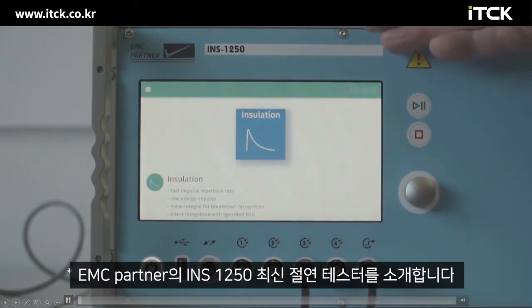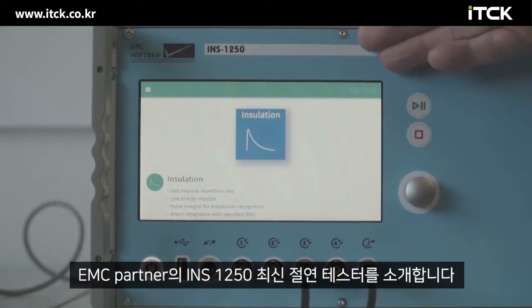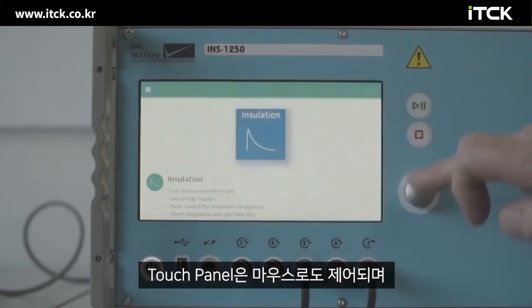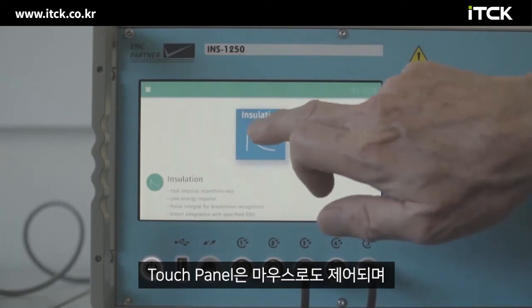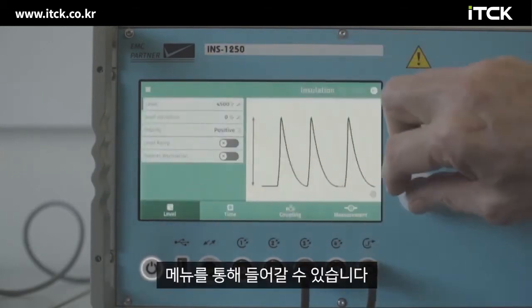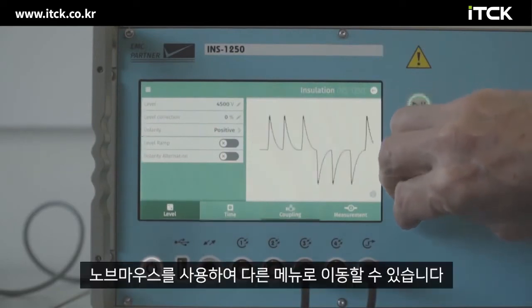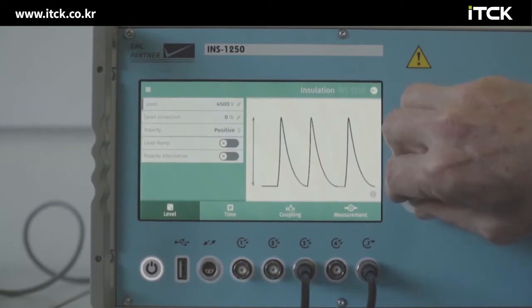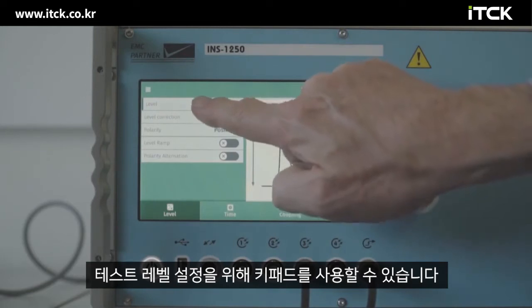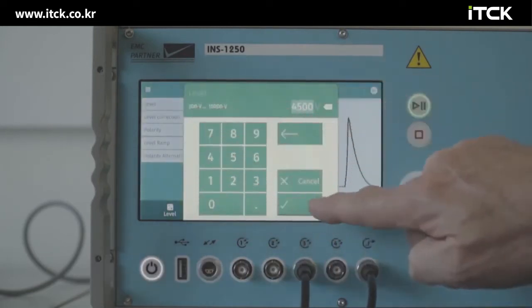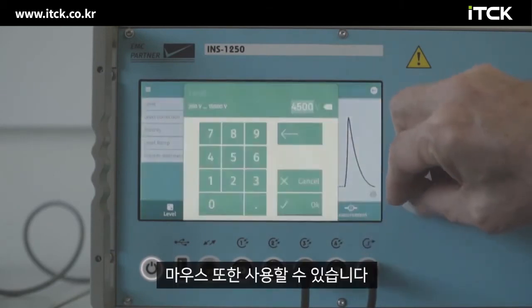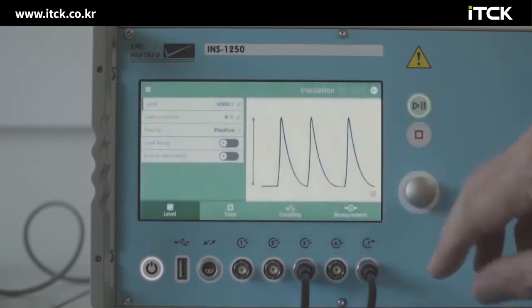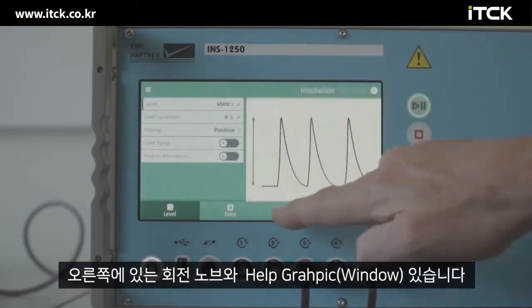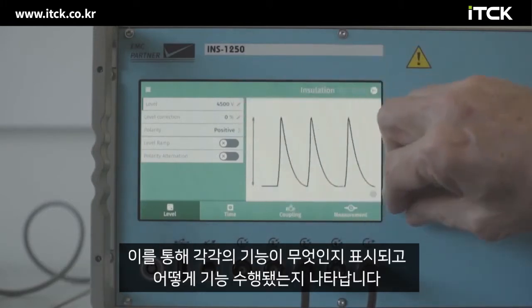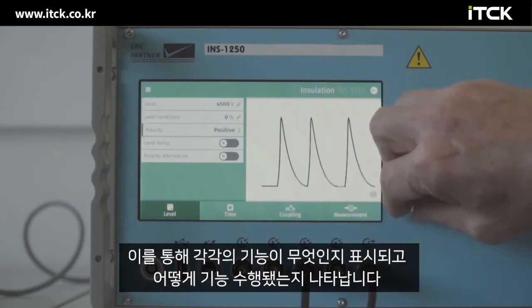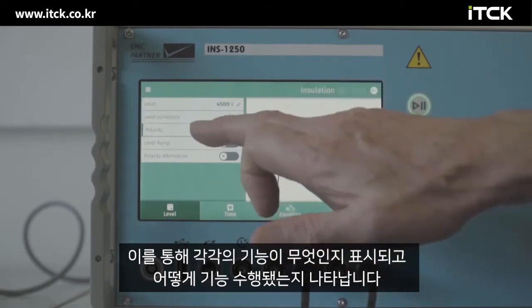So here we're introducing the INS-1250, latest generation insulation tester from EMC Partner. The touch panel is controlled also by the mouse, and we enter through the insulation menu, and then we can move around the different menus using the mouse. To set the test level, we can use the keypad. We can also use the mouse. The rotary knob. We have on the right side the graphic help, so that each function is indicated and an illustration of what the function performs.